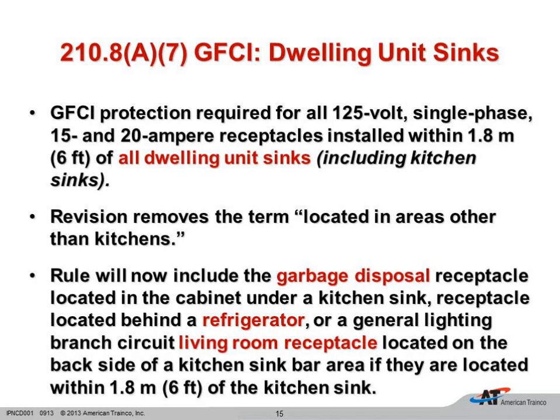How is that going to impact us? Well, if you're like me and you like to put the garbage disposal on a cord and plug, so that it's very easily removed rather than having to lay on our back and disconnect the hardwire, there's going to be a receptacle right below that kitchen sink. That is now going to be required to be protected by a GFCI. If the refrigerator is within 6 feet of that kitchen sink, we are now going to have to put a GFCI protected receptacle for that refrigerator.